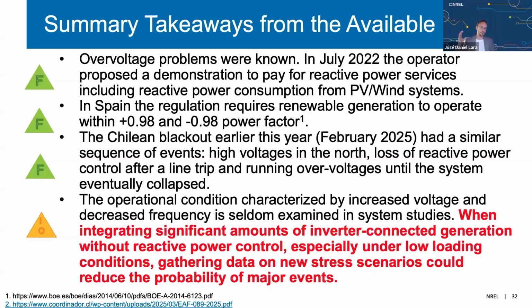Northern Chile was exporting the right amount of power into the middle of Chile, then a line tripped while there were high voltages. The moment we lost this line with high voltages, a sequence of events created over-voltages on the north side, and once the system split in half, it eventually collapsed.